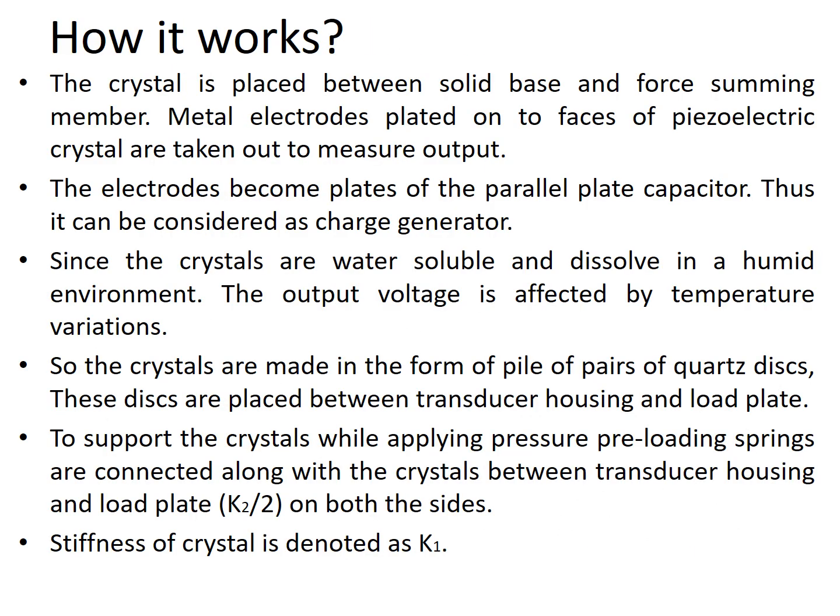So now we are going to see how it works. Already we have discussed how it works. The crystal is placed between a solid base and a force summing member. So we have two ends. One end of the crystal we place on a base, and the other end is where we are going to apply the force. Metal electrodes plated on the faces of the piezoelectric crystal are taken out to measure the output, because we cannot take it directly from the crystal. We have to connect both end electrodes. From there only can we take the output voltage.